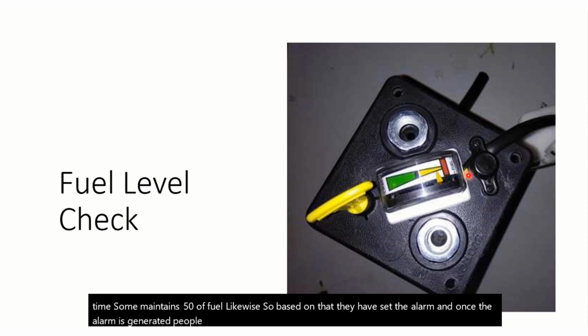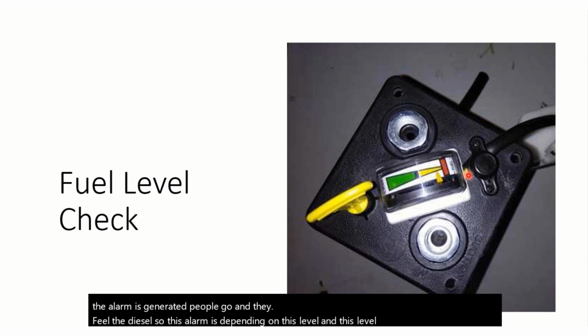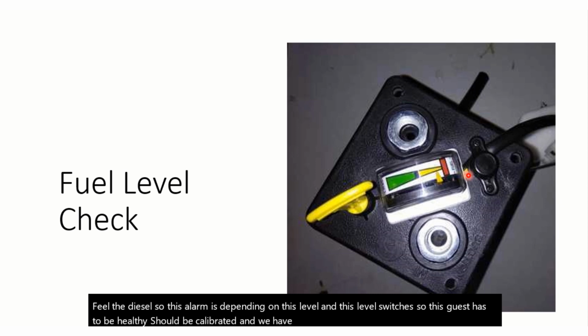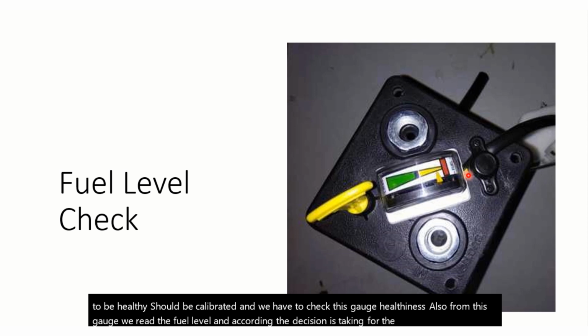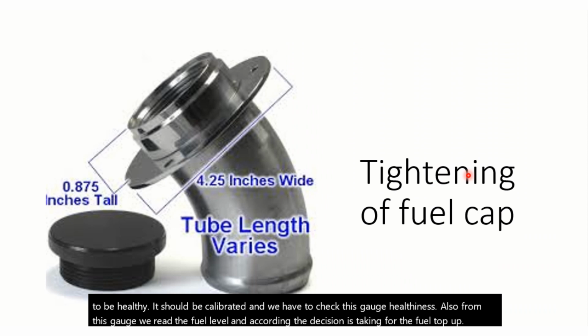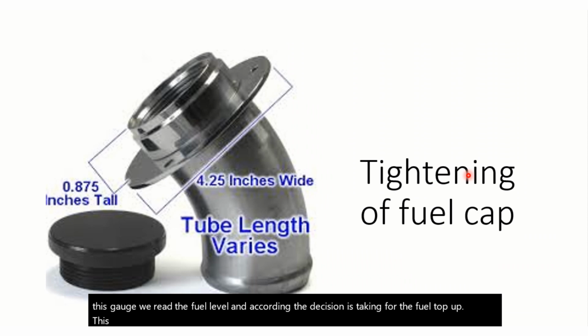So this gauge has to be healthy, it should be calibrated, and we have to check the gauge's healthiness also, and from this gauge we read the fuel level, and accordingly the decision is taken for the fuel top up. This is a fuel cap. While we carry out the maintenance, this fuel cap also has to be properly tightened.